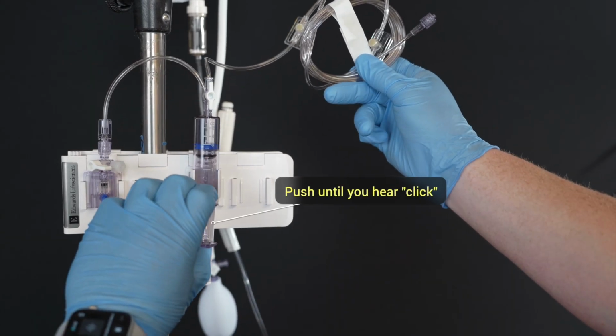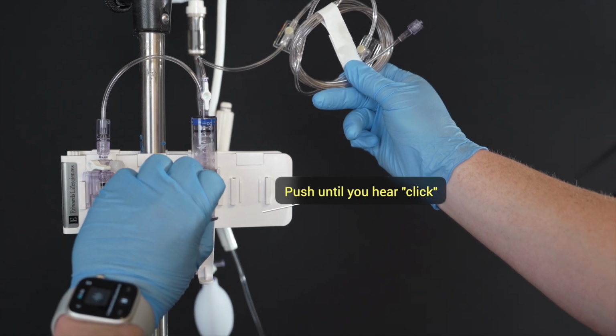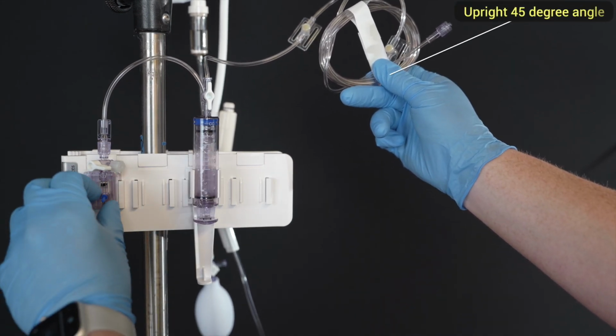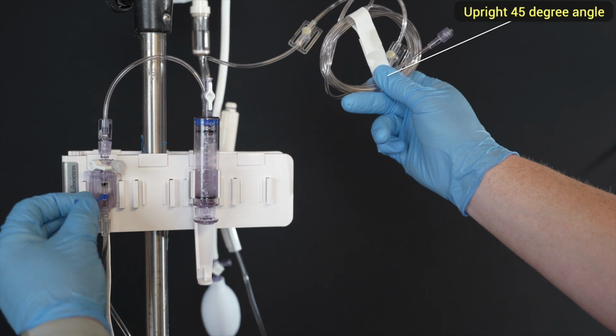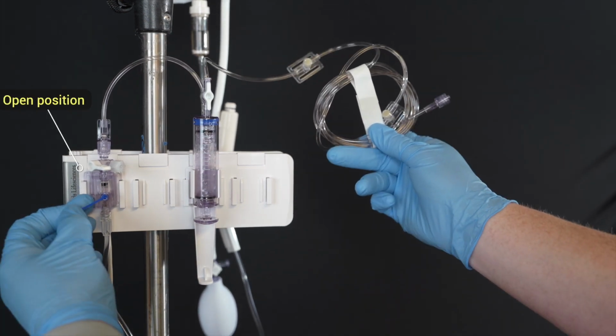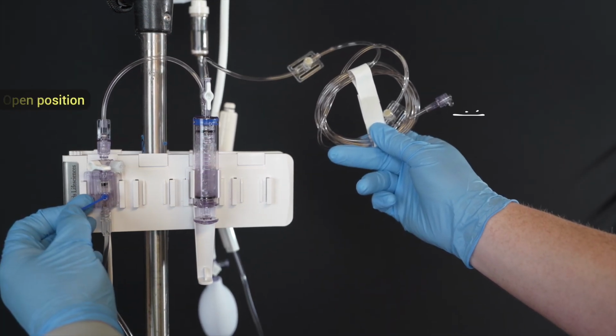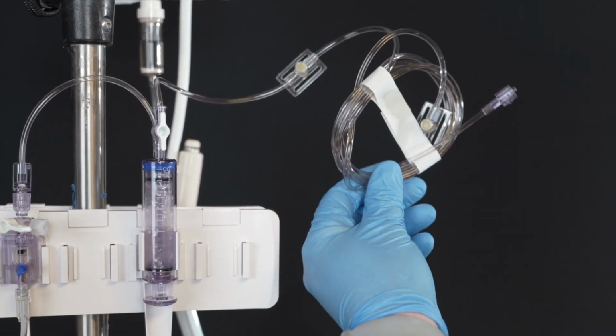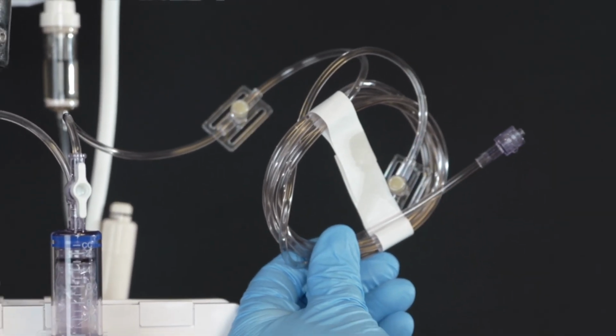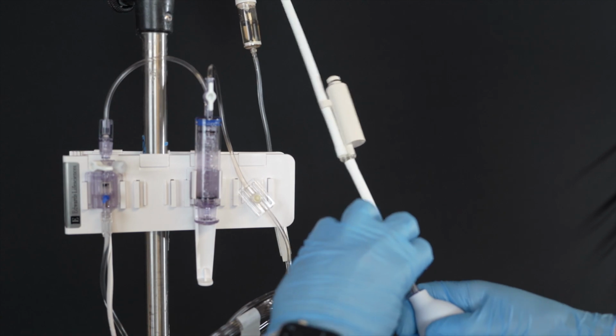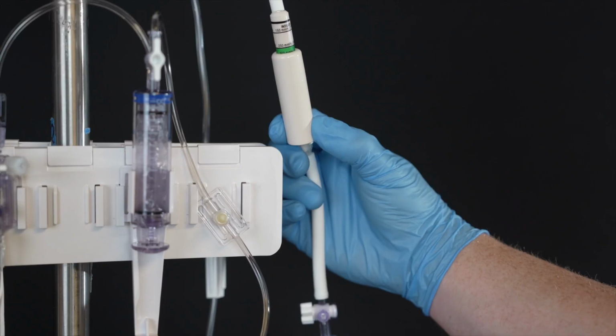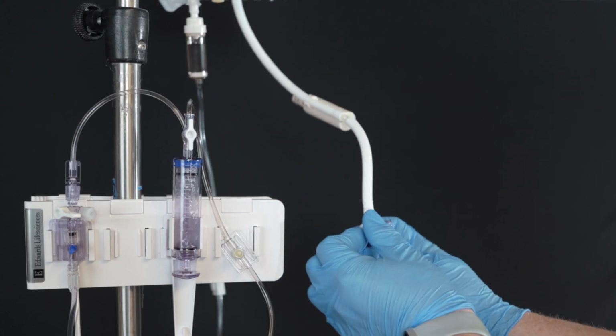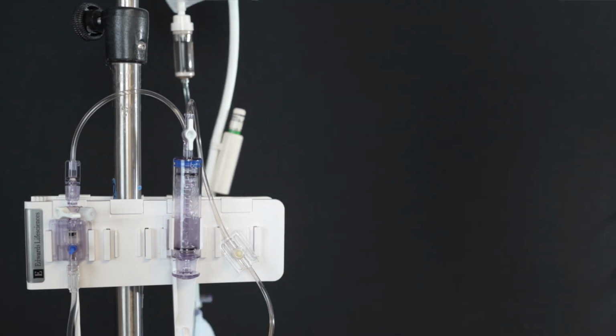Push the reservoir plunger to the closed and locked position until you hear the audible click. Holding the pressure tubing in an upright 45-degree angle, pull the snap tab to flush the remaining part of the line through the end of the tubing. Visually inspect the line to ensure all bubbles are removed. Next, pressurize the IV bag to 300 millimeters of mercury. Turn the stopcock toward the pressure bag to lock off the air pressure.